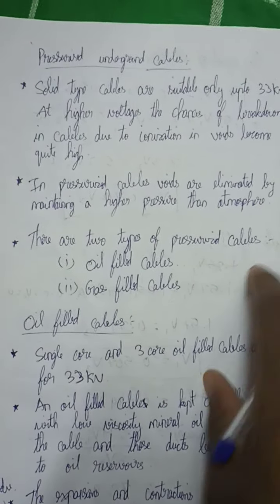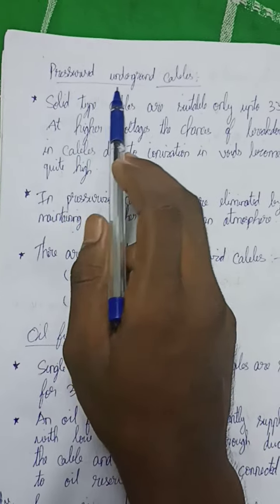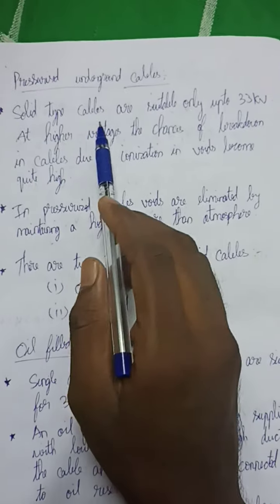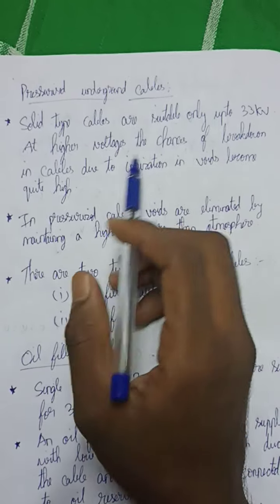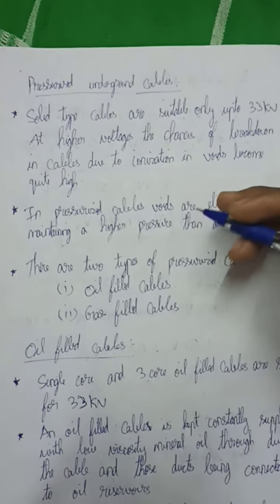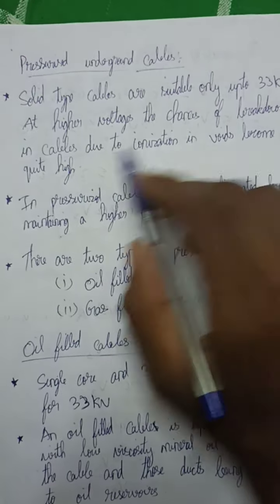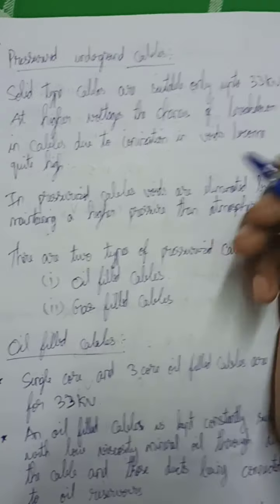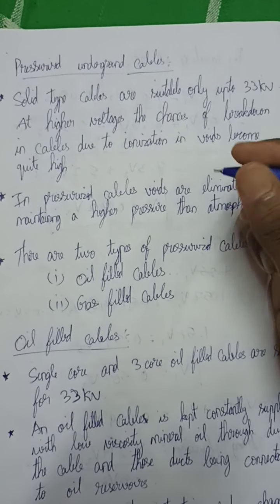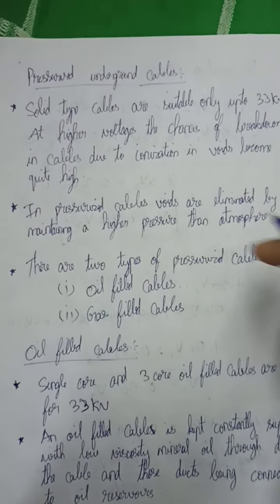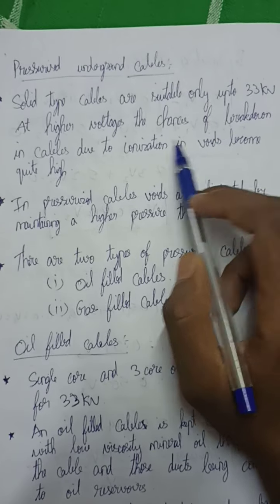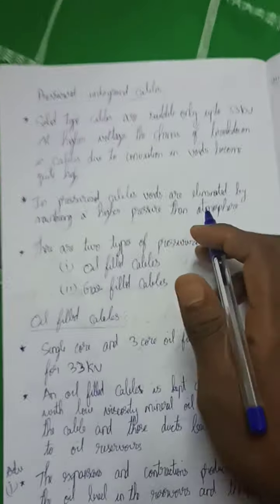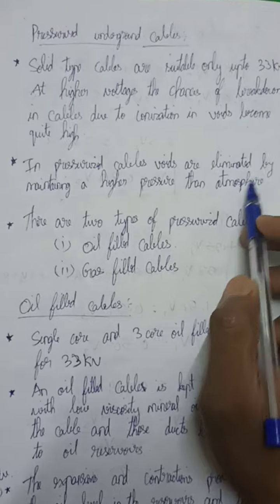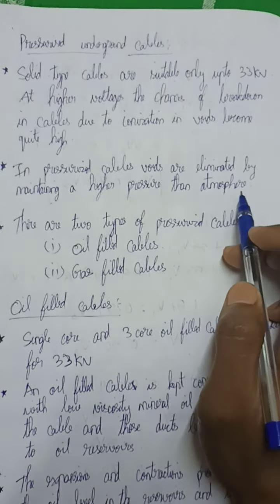Today we are going to discuss pressurized underground cables. Solid type cables are suitable only up to 33 kV. At higher voltages, the chances of breakdown in cables due to ionization in voids become quite high. In pressurized cables, voids are eliminated by maintaining a higher pressure than atmosphere.